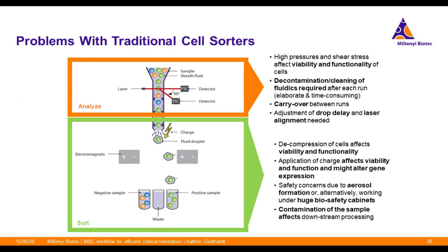Adjustment of drop delay and laser alignment is needed. The decompression of cells affects the viability and the functionality. Application of charge affects viability and function and might alter gene expression. Safety concerns arise due to aerosol forming, or alternatively working under huge biosafety cabinets. Contamination of the sample affects downstream processing.